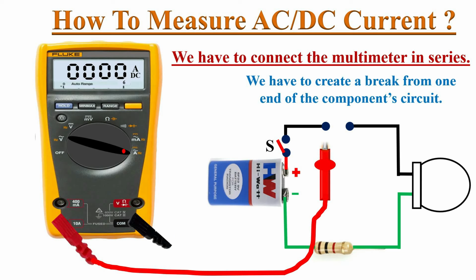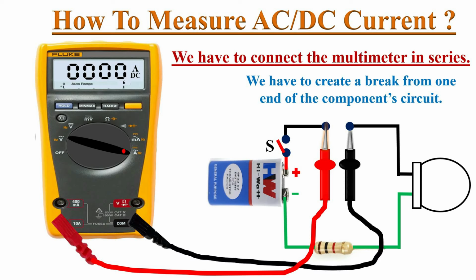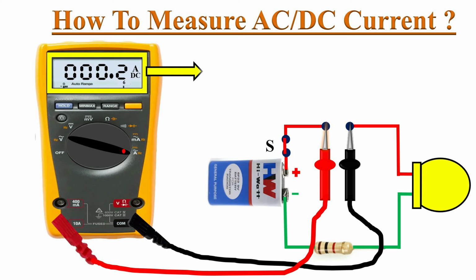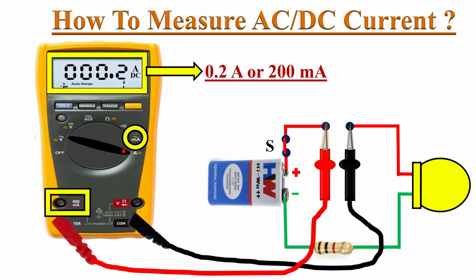Connect red test probe to the break point which is close to the battery's positive and black test probe to the other break point. If you observe over here, now the DMM is in series with this circuit. Switch on this circuit. Here meter display shows current measurement of this circuit. It is 0.2 amperes or 200 milliamperes of direct current. So 200 milliamperes reading is less than this 400 milliamperes level. So we will use milliamperes port and turn the dial to milliamperes position for accurate measurement of current flow.